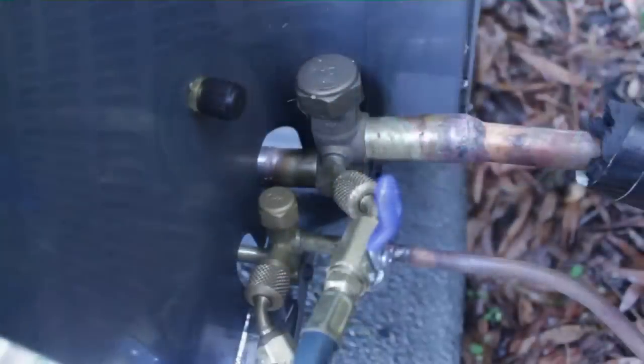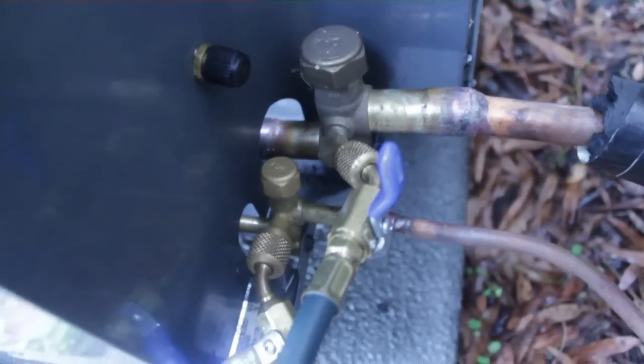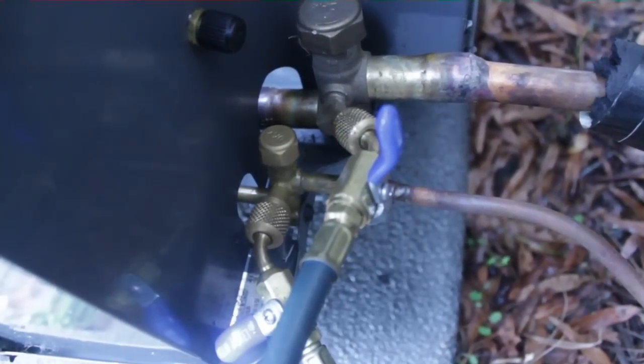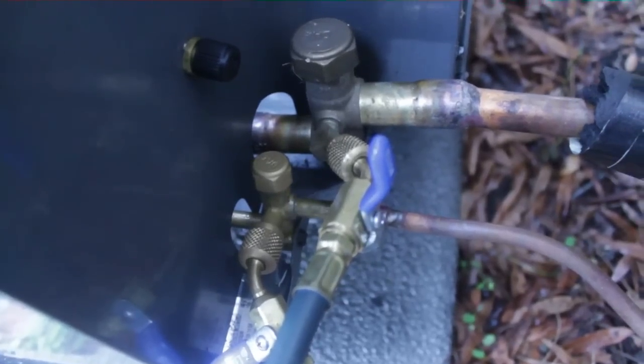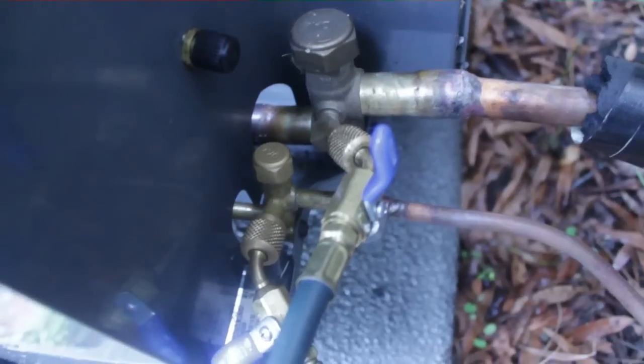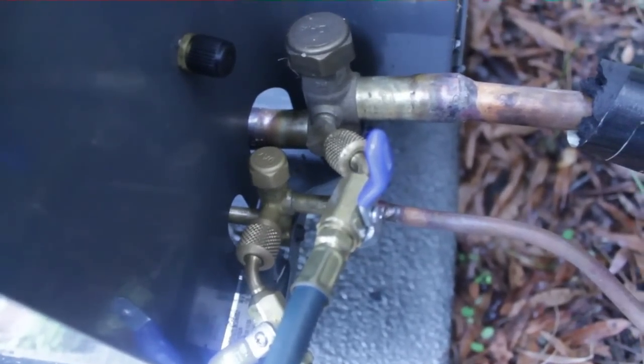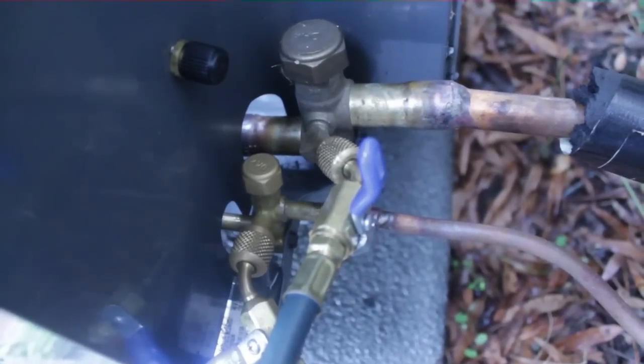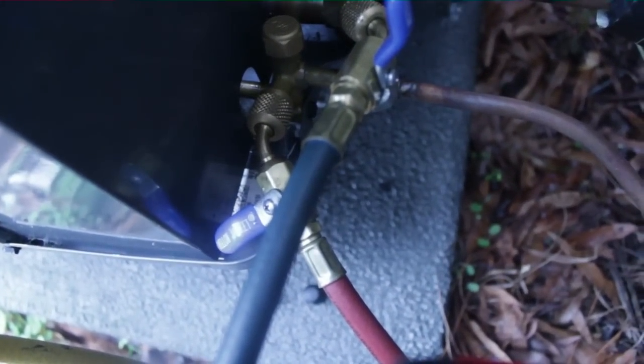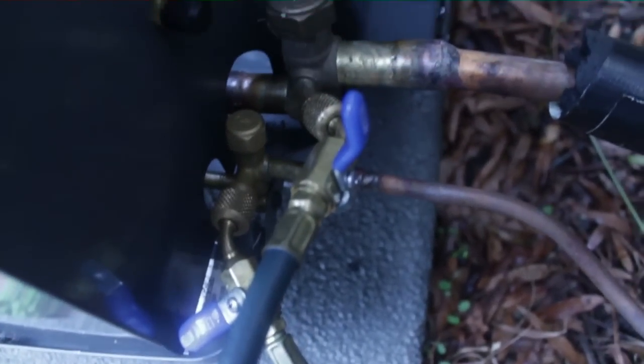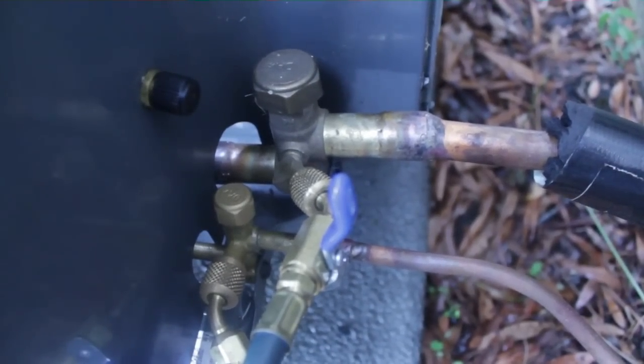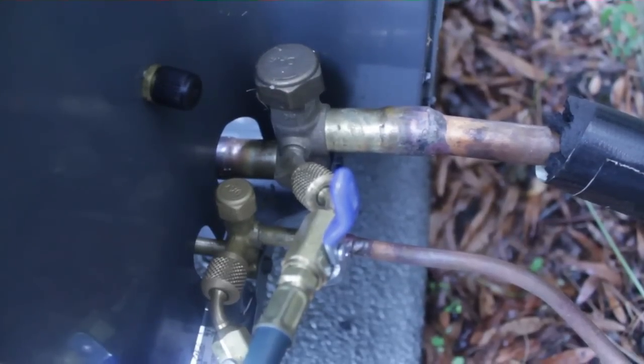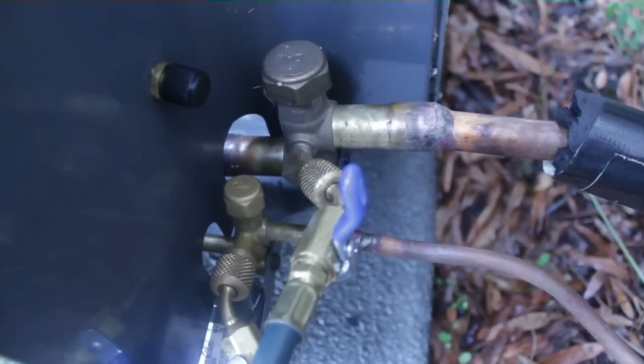You can see we have hoses hooked up here. We have our blue hose from the low side of the gauge hooked to the suction line. This is a cooling hookup—you're running air conditioning and you want to check the charge. Most of you guys are familiar with this method. The red or high side hose is hooked to the liquid line, the smaller copper line.